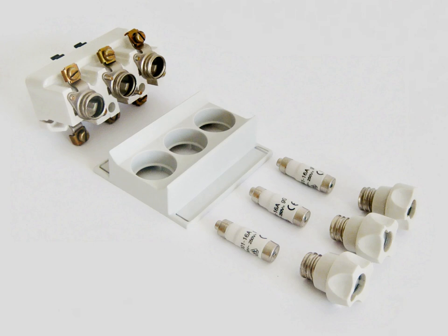They are available rated to break safely for fault currents up to 50 kA RMS, and are intended for use as incoming main protection. D0 type Neozed fuses are similar but have a smaller, cylindrical body. They are available in 3 different sizes with ratings from 2A up to 100A.